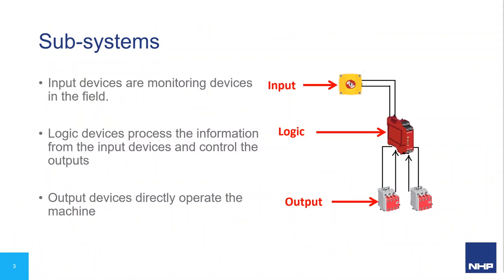A safety control system can typically be broken down into three subsystems: the input, logic, and output subsystems. All safety devices play at least one of these roles. The input devices monitor what happens in the field, the logic devices process the information and determine what to do based on a program, and the output devices actuate when commanded by the logic. This system shows an emergency stop as the input, a safety monitoring relay as the logic, and a pair of safety contactors as the output. The safety monitoring relay determines if the emergency stop is pressed and de-energizes the contactors to remove power from the machine.